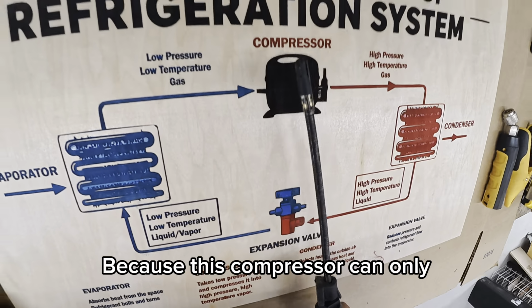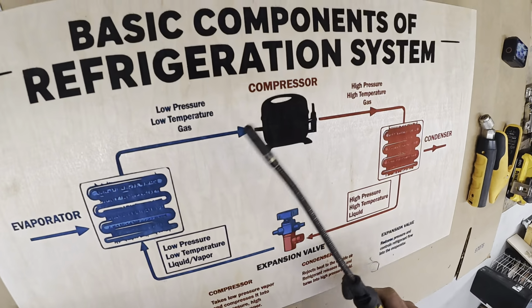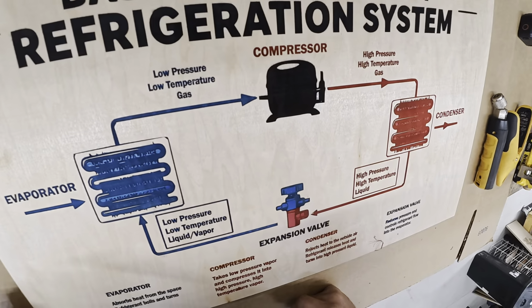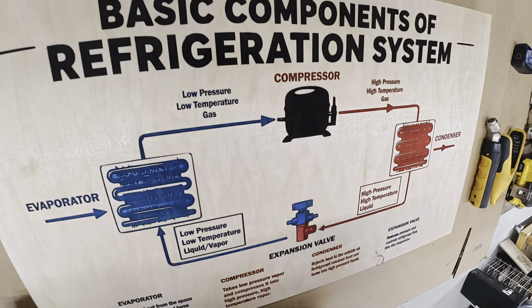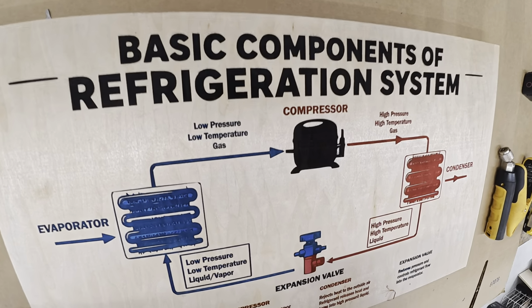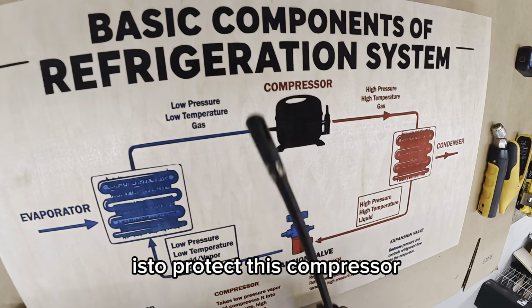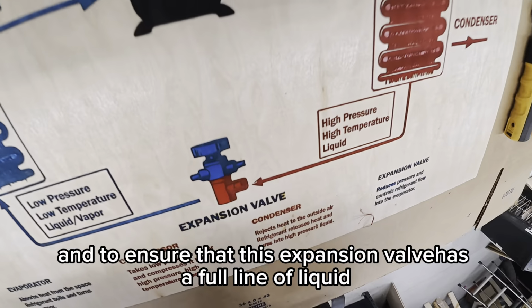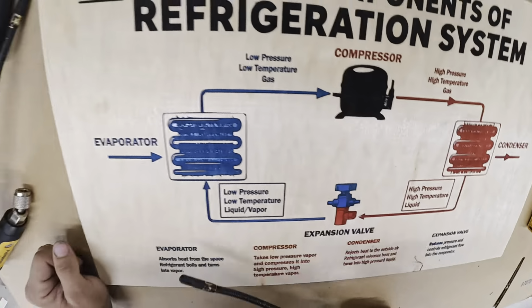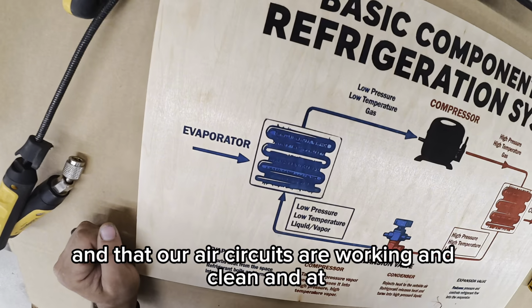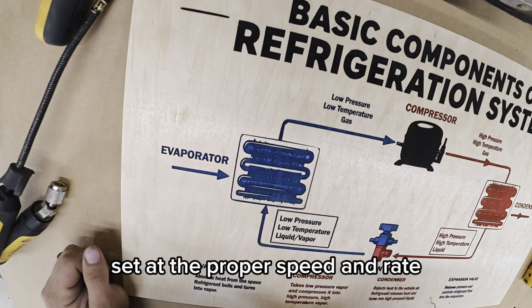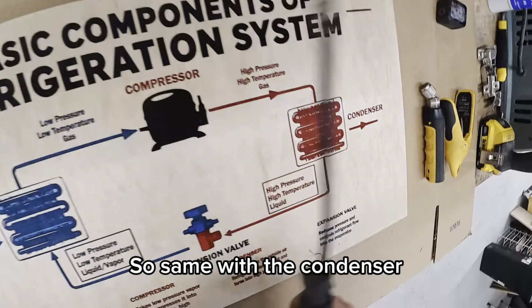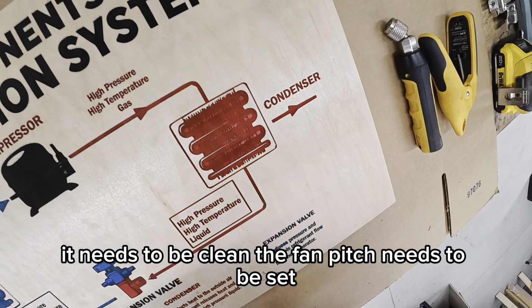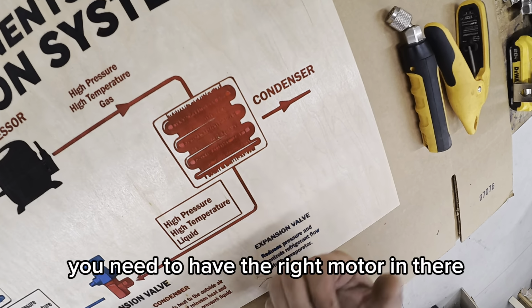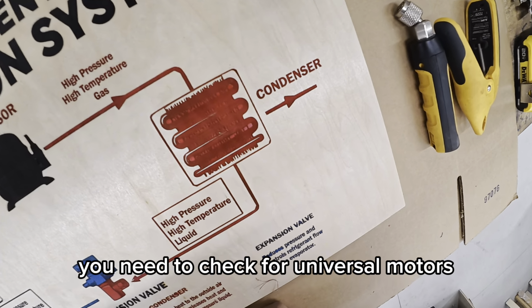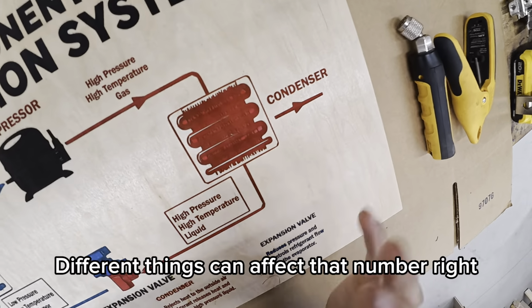Because this compressor can only compress vapor. This compressor cannot compress liquid. So that's why it's very important. Our whole goal in the refrigeration circuit is to protect this compressor and to ensure that this expansion valve has a full line of liquid and that our air circuits are working and clean and set at the proper speed and rate. Same with the condenser, it needs to be clean, the fan pitch needs to be set, you need to have the right motor in there, you need to check for universal motors. Different things can affect that number, right?